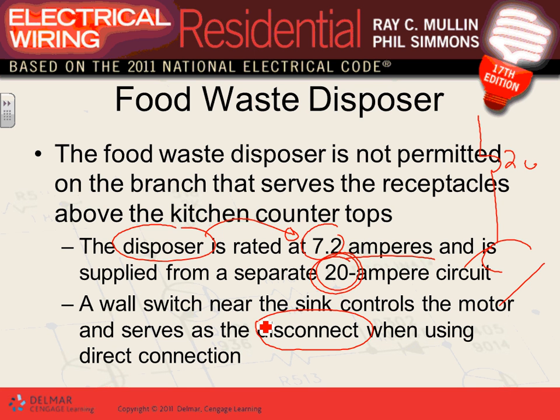So typically for the garbage disposal, what we do is we put a little switch right here, and that switch right next to, above the sink, will act as your on-off controller, as well as your disconnect. It does double duty, the controller as well as the disconnect, so you can disconnect it to work on equipment. Any comments, guys, about the garbage disposal circuit, a 20 amp circuit into a switch like you have wired with me? The way we did it, we put a plug here and we plug it in.